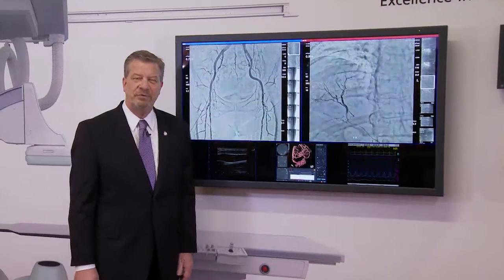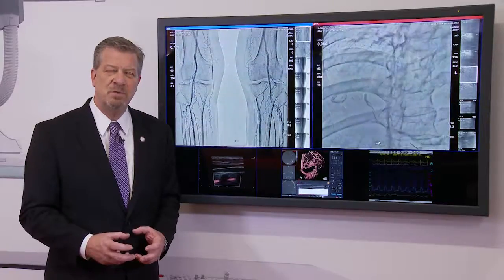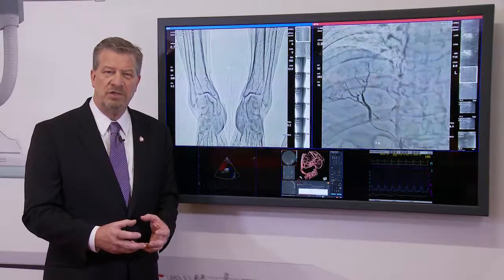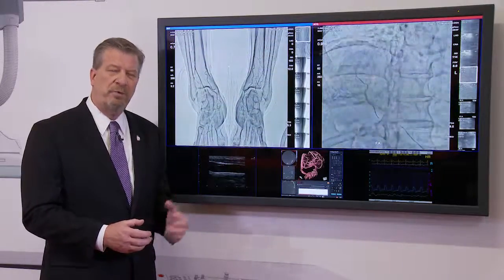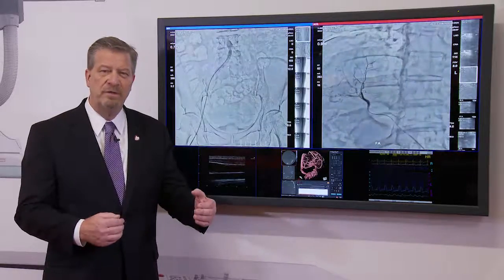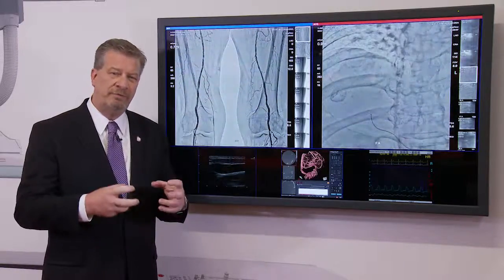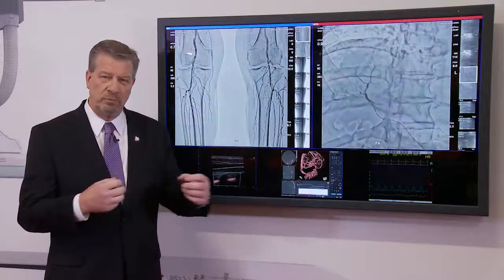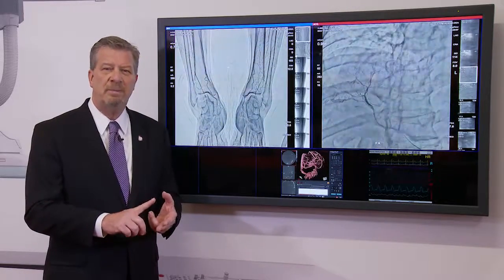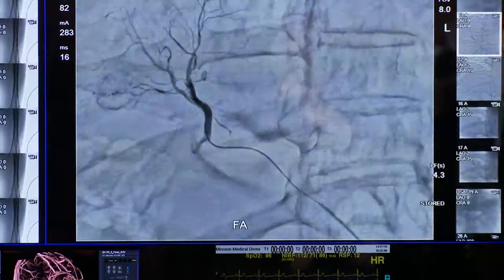Another feature of the Shimadzu Trinias system is a function called RSM-DSA — real-time smooth masking digital subtraction angiography. It's essentially motion correction subtraction. For peripheral angiography, you can inject the patient, acquire the images, and they're subtracted on the fly. If the patient moves, it's automatically compensated so you see great images every time. You don't have to re-inject the patient or re-acquire the study. This also works with two processes we call pendulum and precession on our positioners, for all the abdominal work.